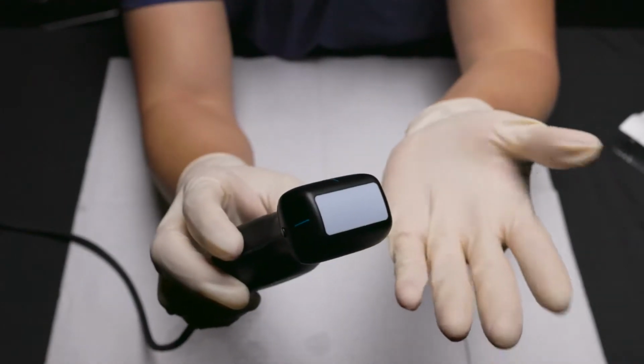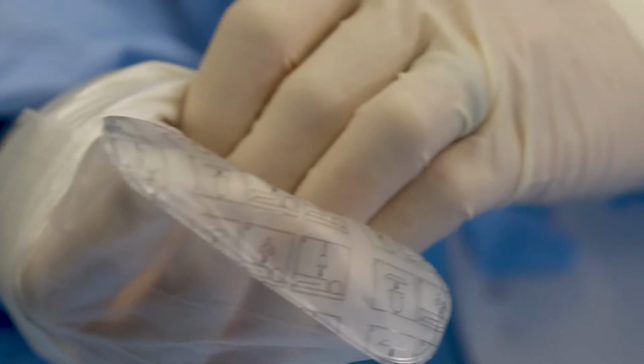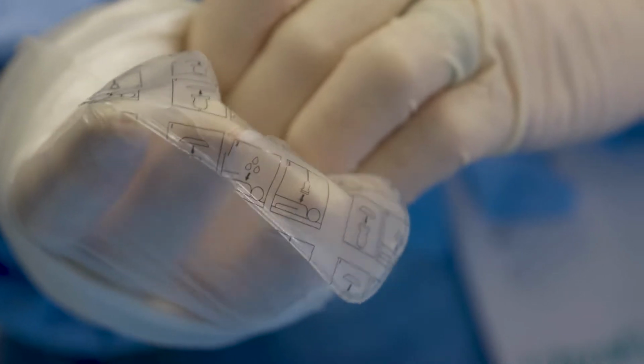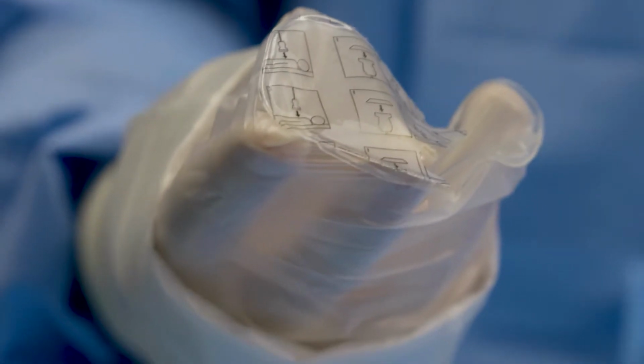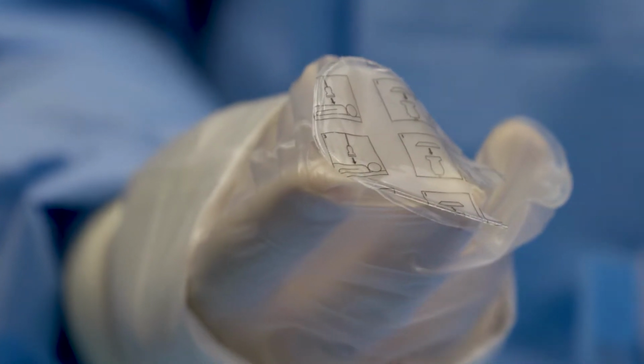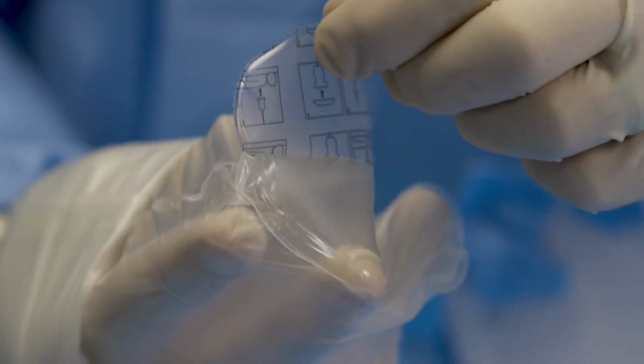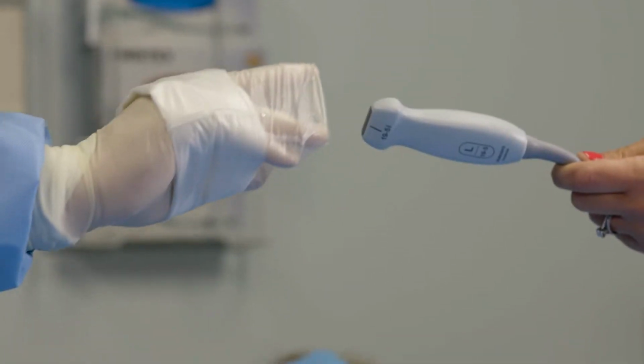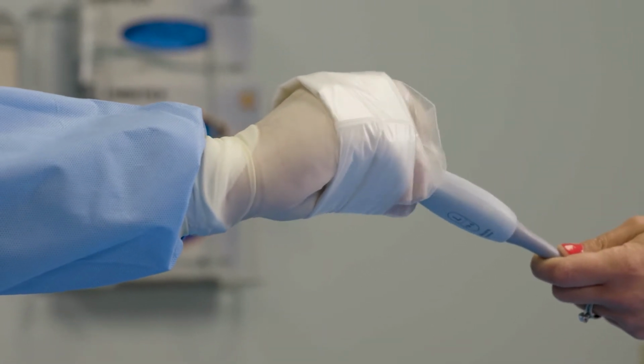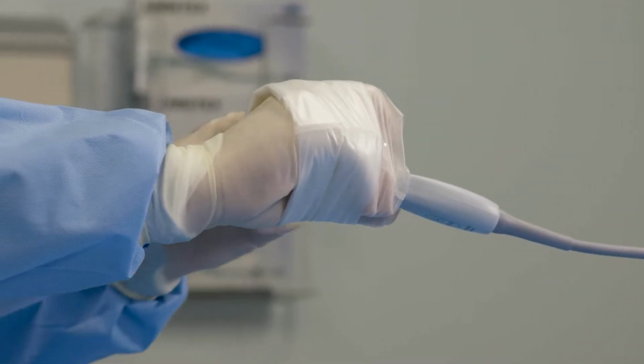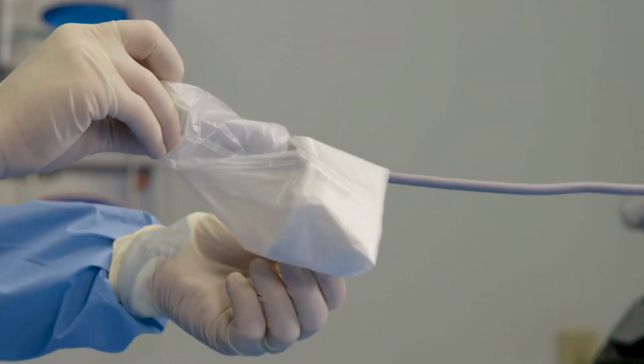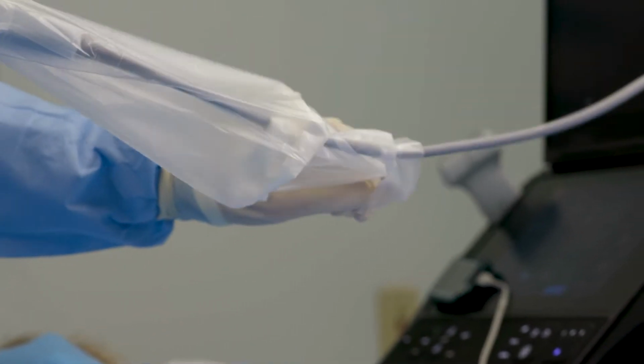When you use the Envision cover, it's very similar to the regular probe covers that we're using now. What you're going to do when you use this cover, you're going to pop up the liner tabs, and that's going to expose the silicone adhesive underneath. This is a very gentle adhesive and will eliminate any air between the transducer and the probe cover, just like the gel serves without the gel.